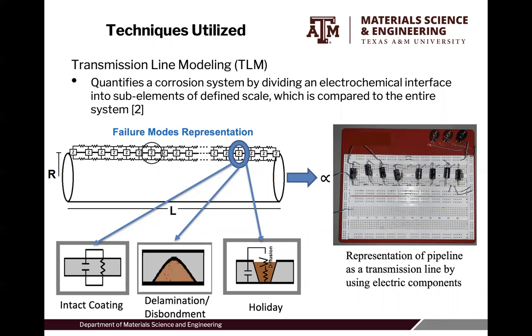With our TLM, we're able to simulate the experiment in software. In this software, we have parameters for the resistance of the coating and the pipe, and we're able to create failure modes. Failure modes include delamination or disbondment, and we can also create holidays. Using the TLM, we were able to create physical electrical components of the TLM model. As you can see, both are proportionate to each other, and this electrical component simulates a 40-kilometer pipeline with failure modes.